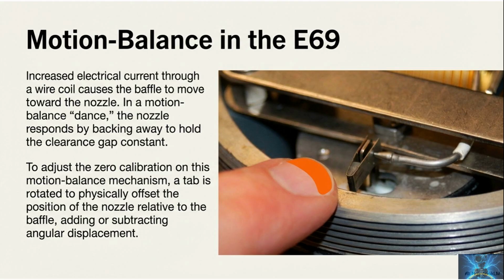Motion balance in the E69. More electrical current through a coil increases magnetic force and moves the baffle toward the nozzle. In motion balance, the nozzle dances back to keep the clearance gap constant. That constant gap is the stabilizing trick that makes the output predictable and smooth. Zero adjustment is done by rotating a tab that offsets the nozzle position relative to the baffle. You are literally shifting the geometry so the balance point lands where you want it.